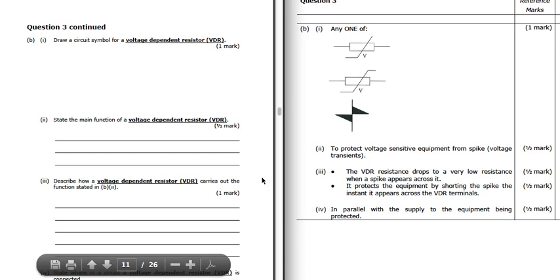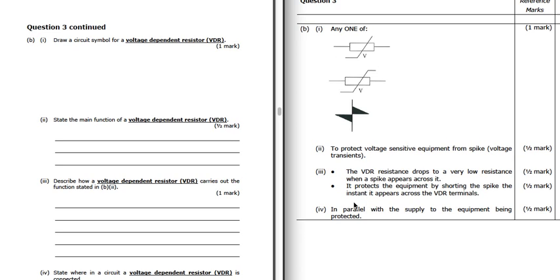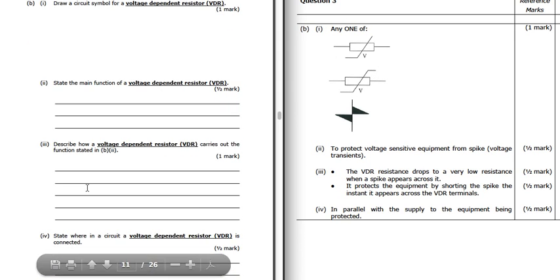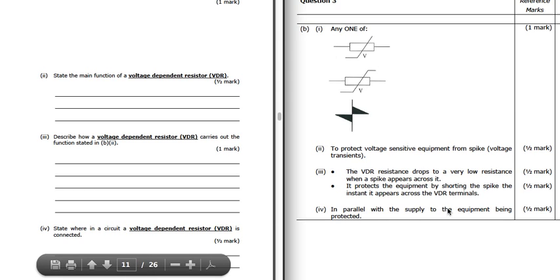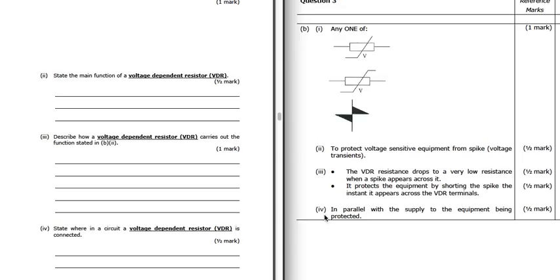How does it do this? So it drops to this very low resistance, and it protects the equipment by shorting the spike the instant it appears across the VDR terminals. So that voltage spike, that lightning strike or whatever, doesn't get to the equipment because this VDR goes short circuit and takes that voltage spike. And where do we connect it? We connect it in parallel with the supply to the equipment being protected. So you'll see it across the supply, across the phase and neutral, before the equipment that we want to protect.